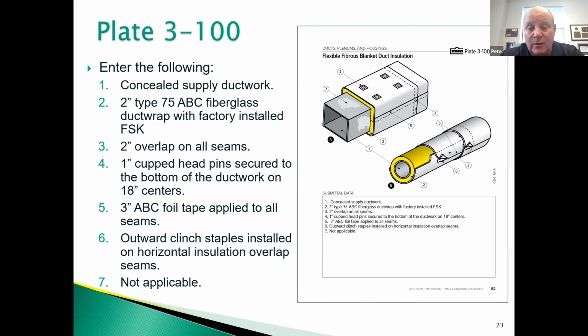Number 1, what type of duct system is it? In this case, we're going to call it concealed supply ductwork. Number 2 is the insulation material - we're going to use 2-inch thick type 75 ABC fiberglass duct wrap with factory installed FSK. Again, you can word it however you like; you don't have to word it exactly the way I have it in this example.